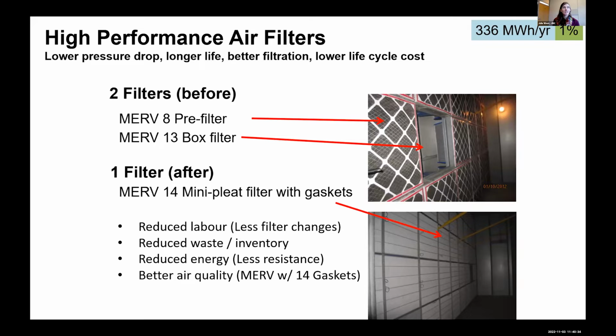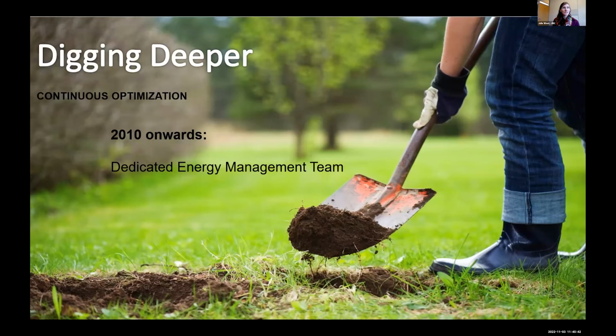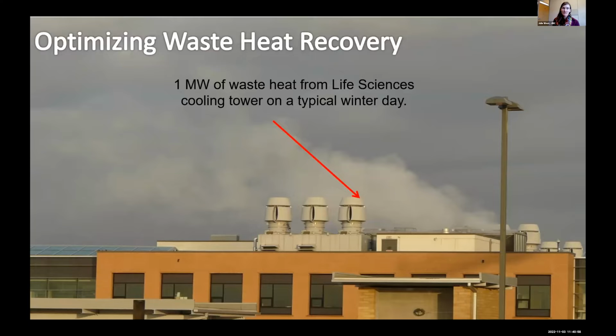And that had pretty substantial savings, roughly 1% for the filters and 1% for the coil cleaning in this building. Digging a lot deeper, we had a dedicated energy management team from 2010 onwards, and so we were able to really look at the buildings in much more depth to figure out how we can save energy. One of the things that was the most obvious at life sciences was that we were rejecting a lot of waste heat from the building. Roughly 1 megawatt of waste heat was rejected from life sciences on a typical winter day, and we could be using that heat within the building.